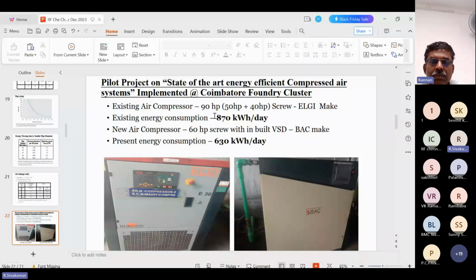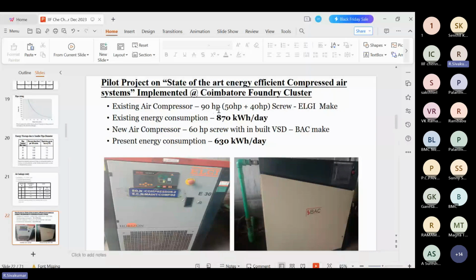Now we suggested changing the 90 HP with a single 60 HP compressor inbuilt with VSD, that is the variable speed drive. This compressor uses internal permanent magnet motor technology. The manufacturer is in Coimbatore only, for both air compressors. So now it is implemented with the 60 HP screw compressor, IPM model, inbuilt variable speed drive. The present energy consumption is 630 units. Almost 240 units were saved in a day.